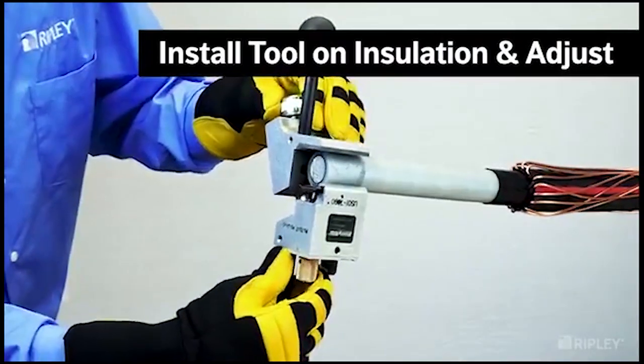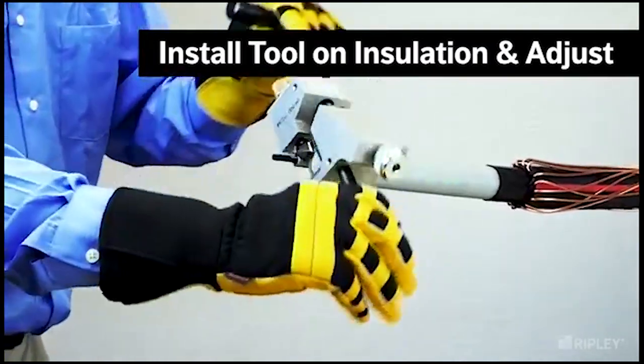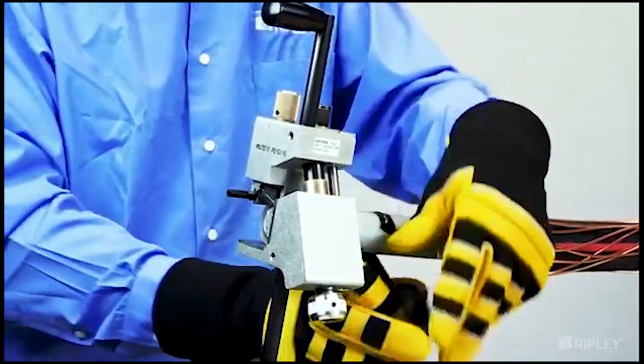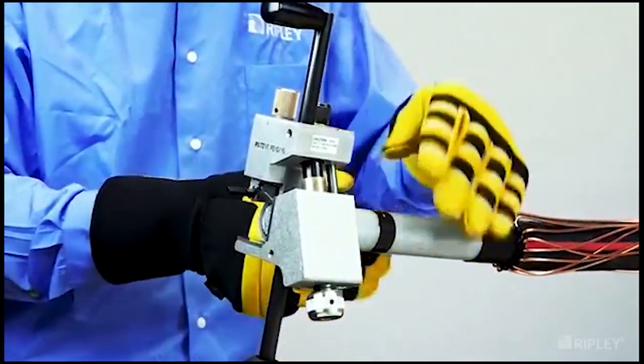Re-install the Infinity around the insulation and re-adjust the blade settings with the blade depth 1-32 of an inch to 1-16 of an inch above the conductor. Set the blade angle to 10 degrees.